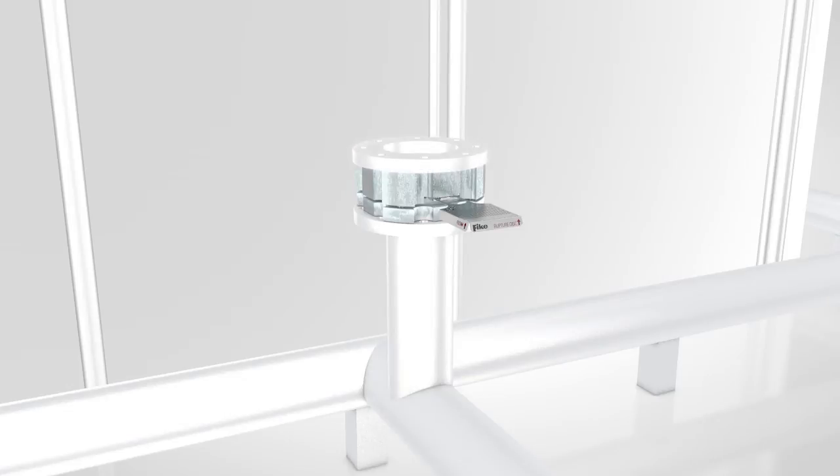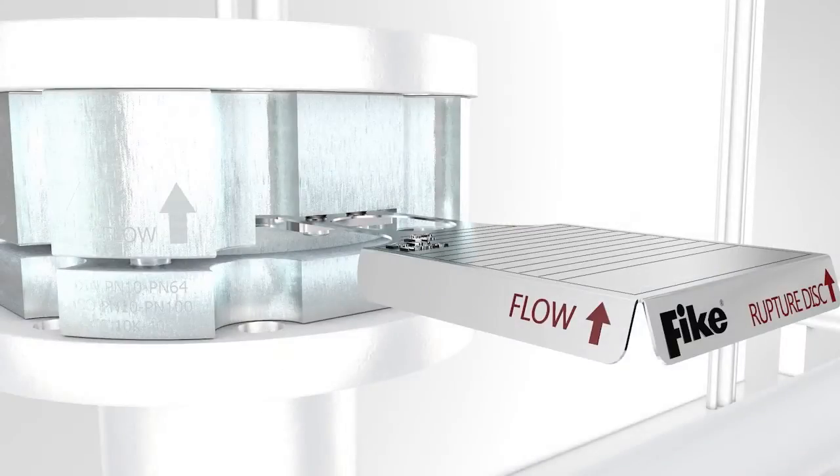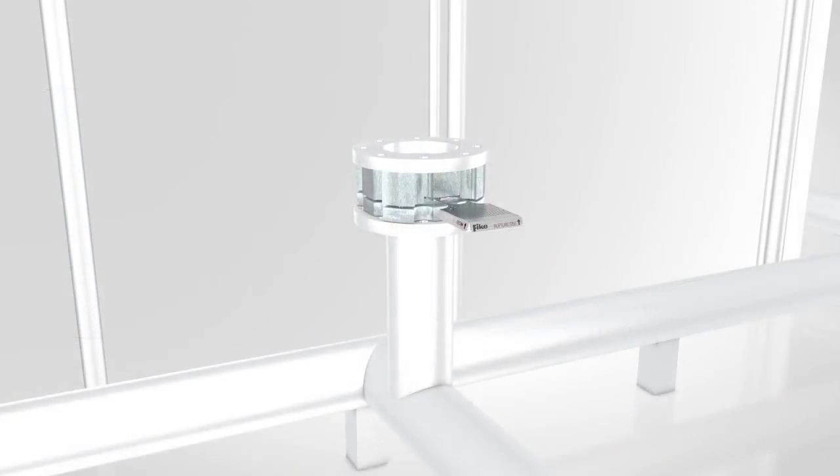Gaskets that are subject to cold flow are not recommended. Carefully place the rupture disc assembly between the piping flanges. Check to ensure the holder flow arrows point downstream.